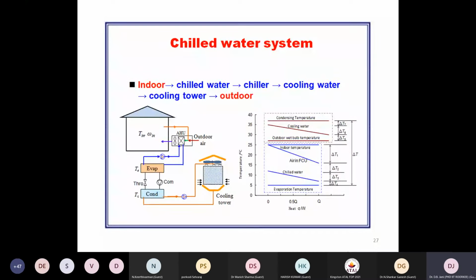Some central VCR system is located, through which chilled water is made available at a temperature of 5 to 10 degrees, and the water is easily conveyed with the help of a pump to every outlet of the different rooms or compartments. It is the easier way, saving insulation cost as well as giving better conveying with the help of a pump instead of circulating the refrigerant to the different outlets.